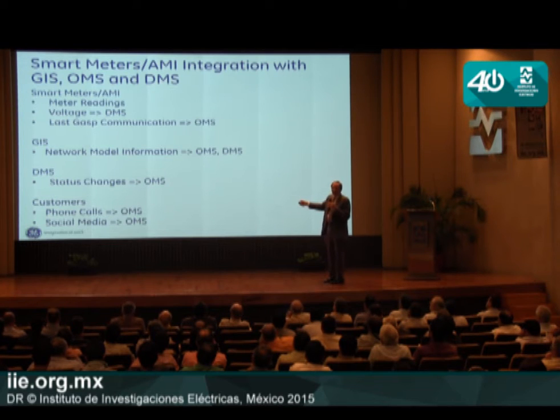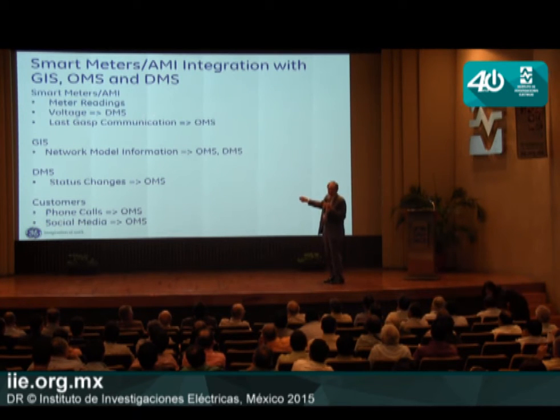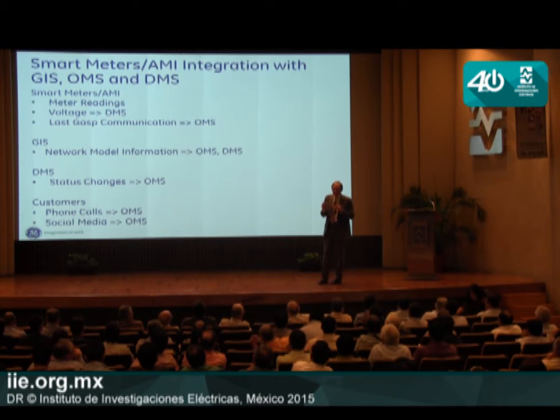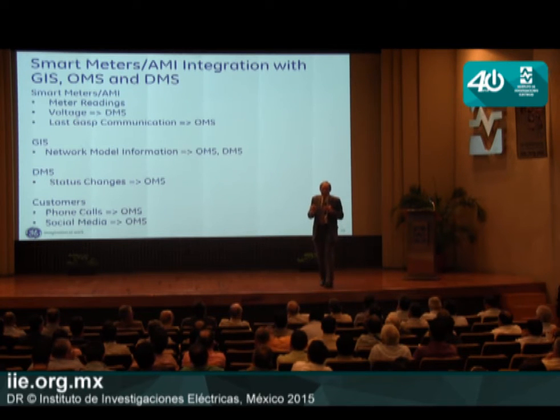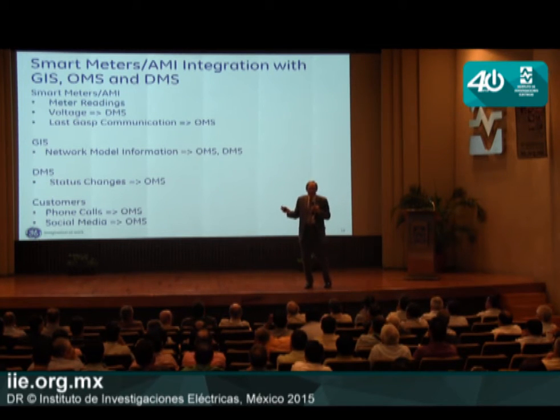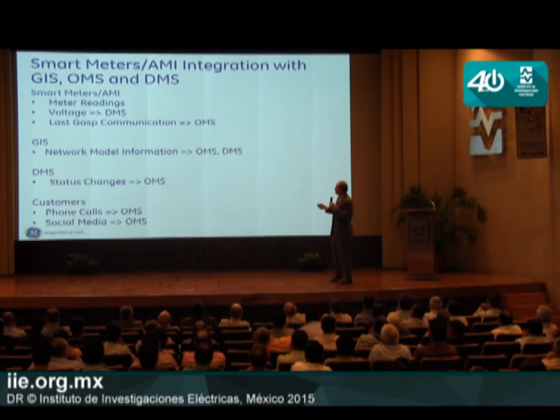The other thing, and this is really important for an outage, is every smart meter has enough energy in it once voltage is lost to have one last gasp communication, right? So there's enough energy in a meter, right, that when there's an outage, there's enough energy for one final communication upstream to the utility, and we send that information to the outage management system. We don't need phone calls from customers.